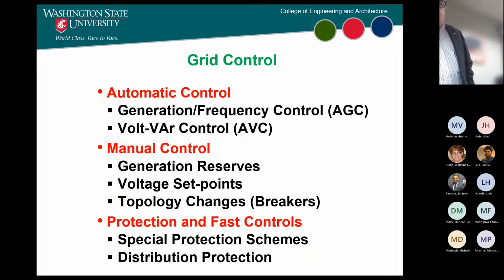Then there's a whole bunch of controls outside this domain, meaning protection control, things that operate because certain conditions occur. So you trip a generator because you suddenly get a short circuit and overcurrent on the generator, then you trip the generator. That's the kind of protection system. So what's happening now?